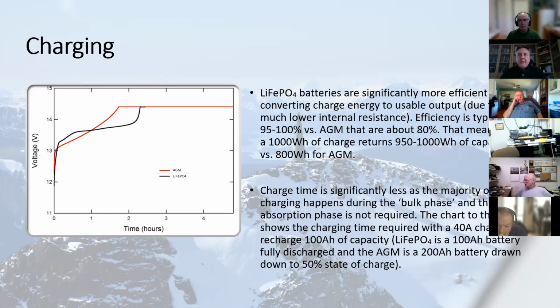You can see the red line, the AGM, the charging happens a little faster up to that full sort of fully charged voltage, but then there's a long absorption phase required when charging AGMs to maintain that voltage after the charge goes away. So the total time to charge the AGM in this example is a full 5 hours for them to be at their 100% state of charge.